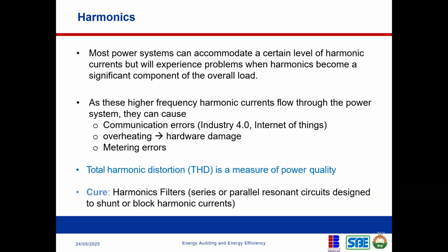Now, when you notice that you have a higher THD, what is the solution? The solution is a harmonics filter. You introduce the harmonics filter to filter them out and correct that signal, that sine wave, back to its normal and fundamental frequency. A harmonics filter is just a series or parallel resonance circuits designed to shunt or block harmonic current.